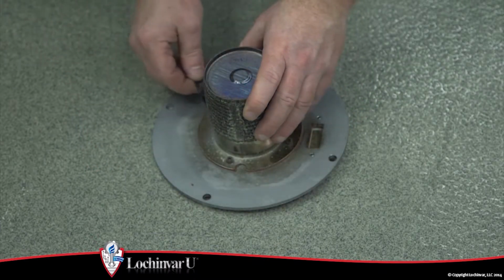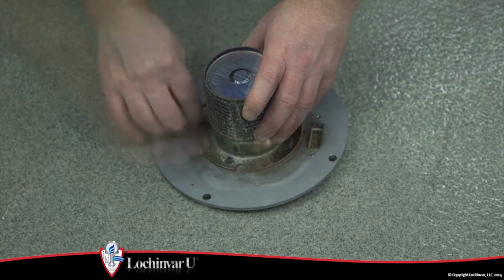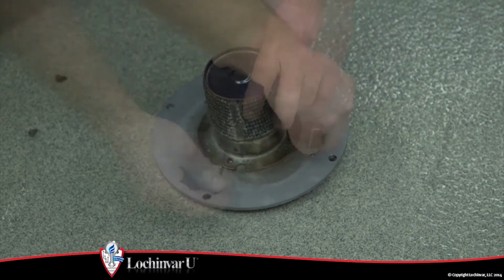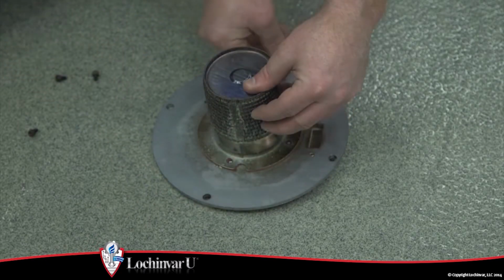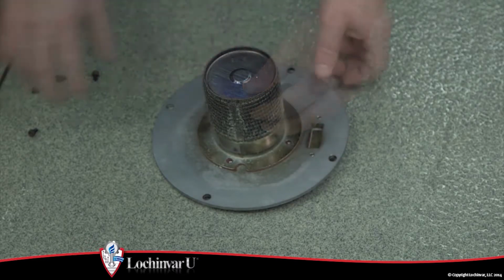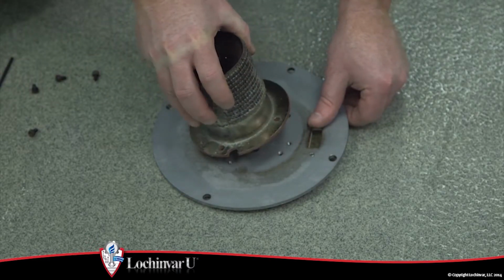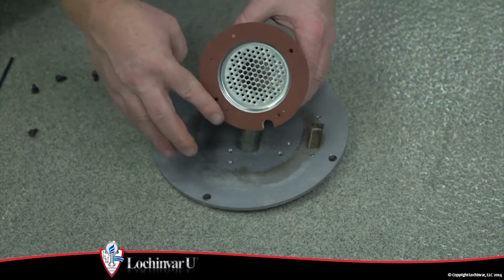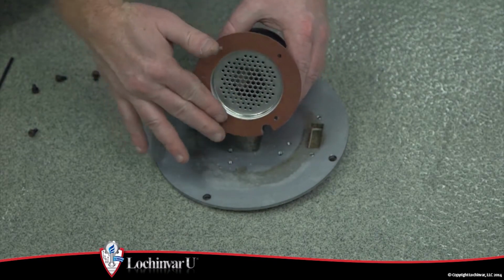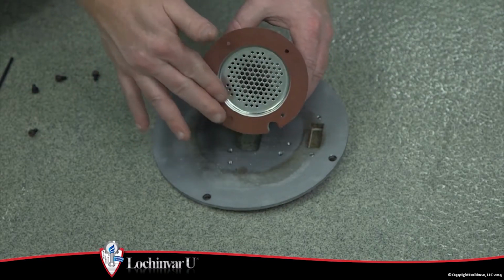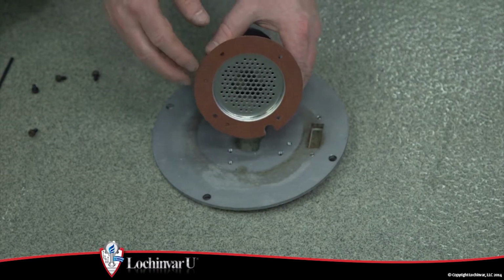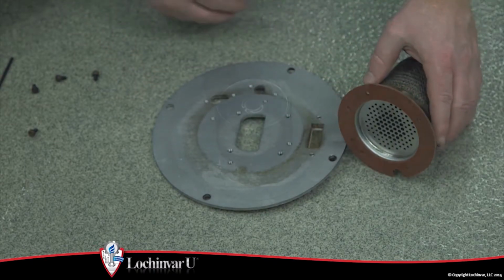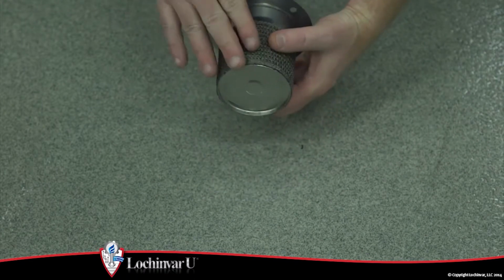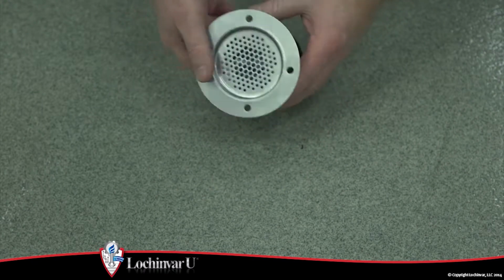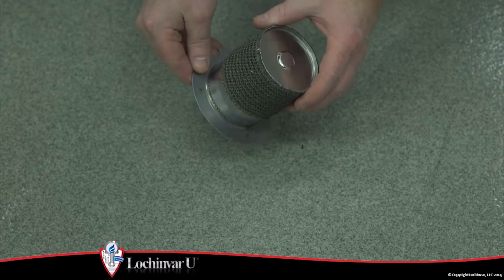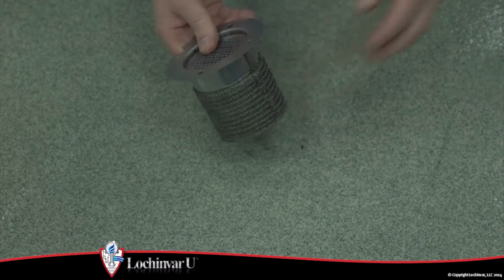Now, using an Allen wrench, remove the screw securing the burner to the heat exchanger door. A gasket is used to seal between the burner and the heat exchanger door. Care must be taken not to tear or damage a gasket. If a gasket is damaged or torn, then it must be replaced. Once removed, inspect the burner for any physical damage. If the burner is damaged, it must be replaced.